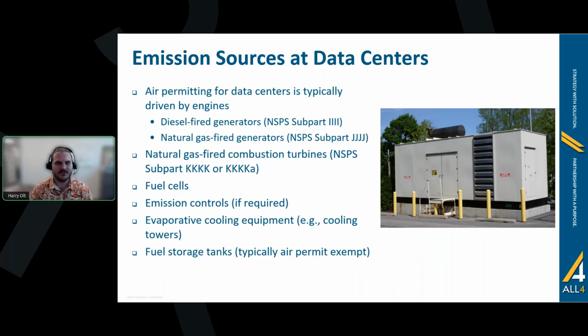So, what are the emission sources of interest at a data center that would require air permits? Air permitting for data centers is primarily focused on the engines that drive emergency generators to provide backup power to the facility. Some facilities are also using them in a non-emergency demand response or prime power capacity if the engines meet the applicable emissions requirements. These engines are typically either diesel fired and subject to NSPS Quad I, or natural gas fired and subject to NSPS Quad J. Some data centers are exploring the installation of natural gas fired combustion turbines to provide on-site power generation in order to supplement or bridge power from the grid.